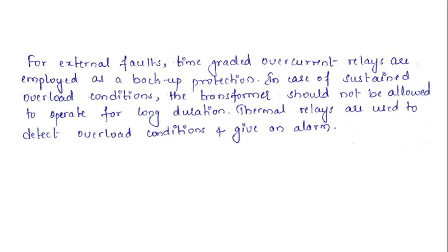For external faults, time graded overcurrent relays are employed as a backup protection. As we have already discussed in previous lectures, in the time graded system, from the distribution side towards the source side, we give the operating time of the relay in increasing order. In case of a sustained overload condition, the transformer should not be allowed to operate for a long duration. Thermal relays are used to detect the overload condition and give an alarm.